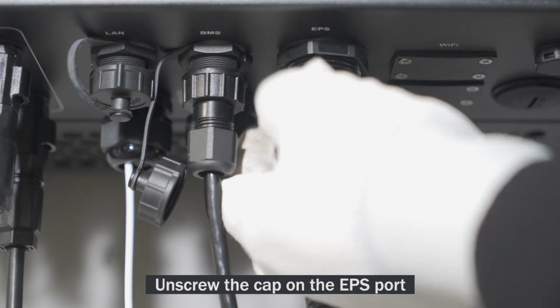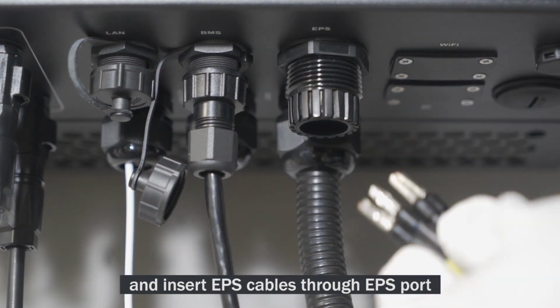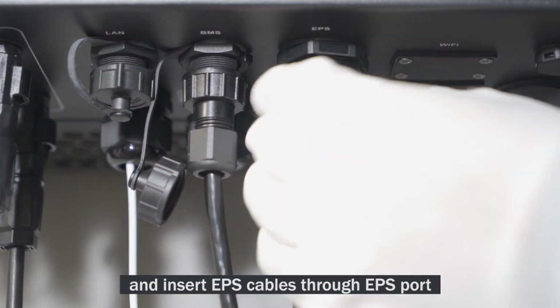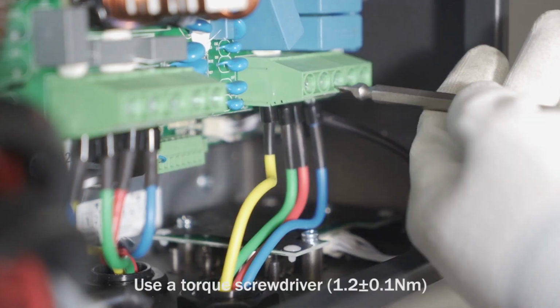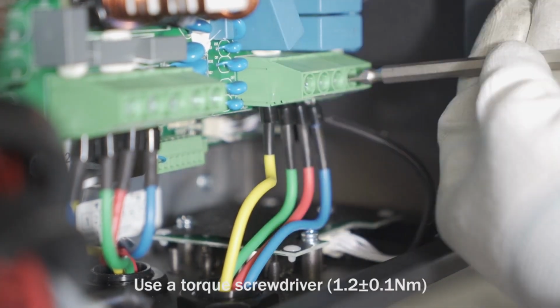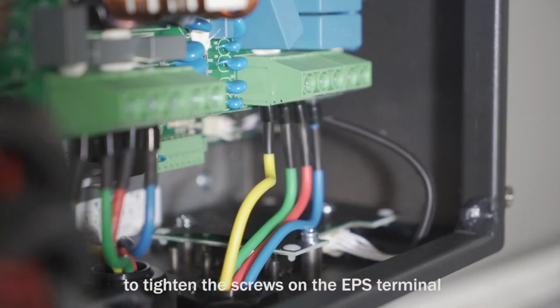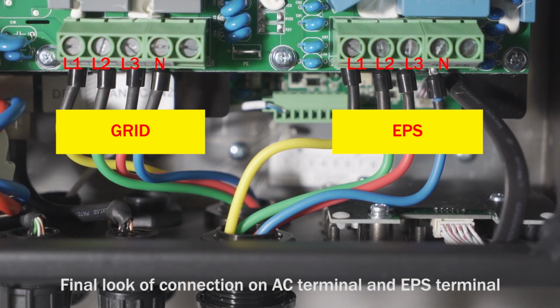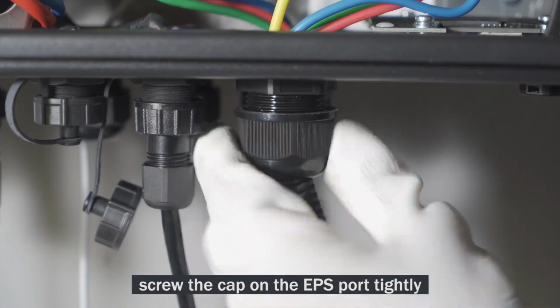Unscrew the cap on the EPS port and insert EPS cables through the EPS port. Use a torque screwdriver to tighten the screws on the EPS terminal. Final look of connection on AC terminal and EPS terminal. Screw the cap on the EPS port tightly.